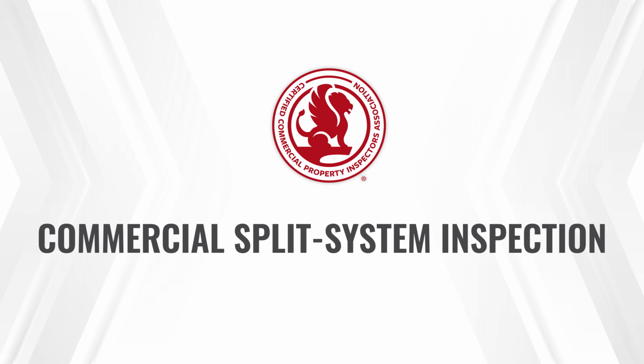There are two different approaches you can take when inspecting an HVAC system. One is doing it by yourself, which is very common. In that approach, I come up on the roof and start inspecting the condition of each unit, gathering data plate information, and performing a ComSOP inspection of this section. Because this is a split system, once I'm done up here I'll go down into the occupancy, since each occupancy has units that need to be checked as well.